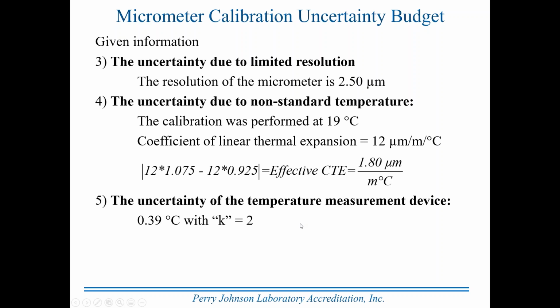The uncertainty of the temperature measurement device. Now, where does this come from again? It comes from the calibration certificate for the temperature measurement device. We found it to be 0.39 degrees C with K equals 2.